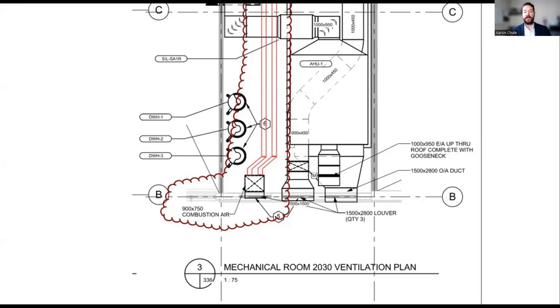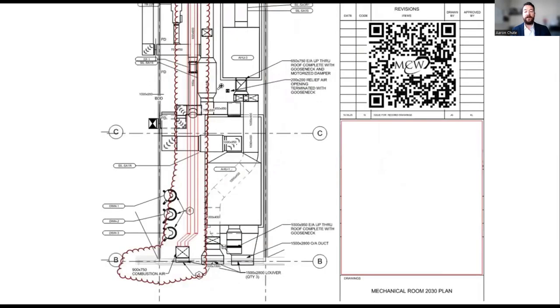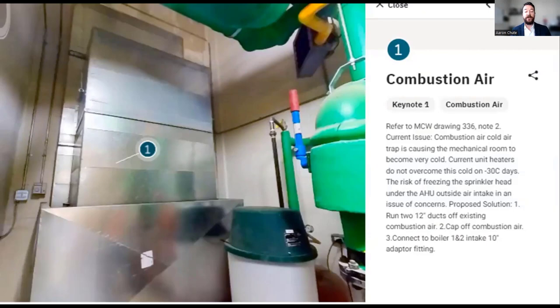Here's an example of one of our projects — a drawing for an existing school mechanical room where the original installation allowed an outdoor combustion air duct to freeze a sprinkler line. This project site is about a two-hour round trip from our office, so limiting site visits was preferred. This drawing is pretty typical, with one big improvement: a QR code we added to allow bidding contractors to virtually visit the site. Within that 3D model, we included our drawing keynotes to itemize what was required to bid on — including the outdoor duct requiring modification to prevent freezing.